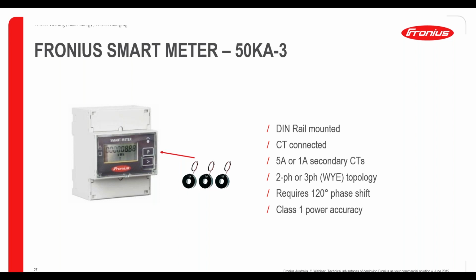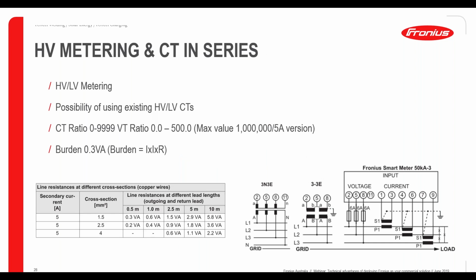It comes with a class 1 power accuracy, so it's not as accurate as a revenue grade meter, but it's nearly there. If we go further, why is this important? Well, this meter can be deployed in what we call HV metering scenarios. Why and how can that be done? The picture on the bottom right shows the typical wiring scenario. This is an extract from the manual. If you look at picture 3-3E, this shows the typical voltage transformer option that we have. So instead of measuring an LV Y topology, you could measure an HV site by using VT transformers.